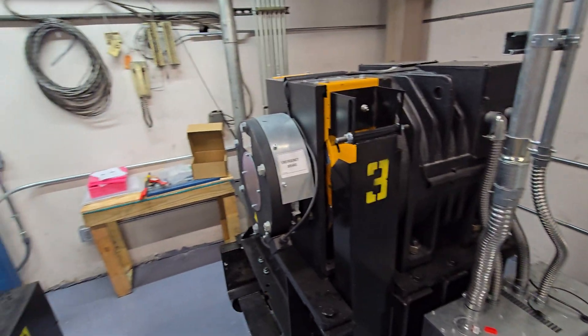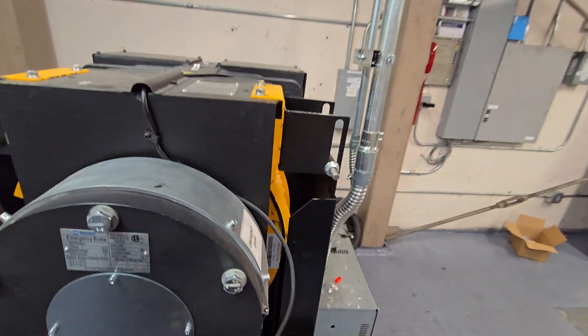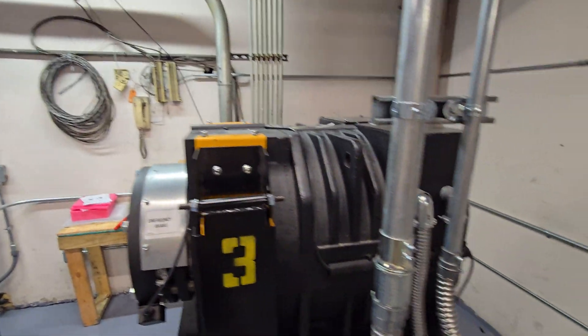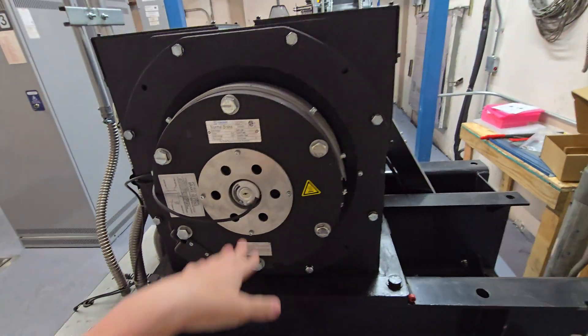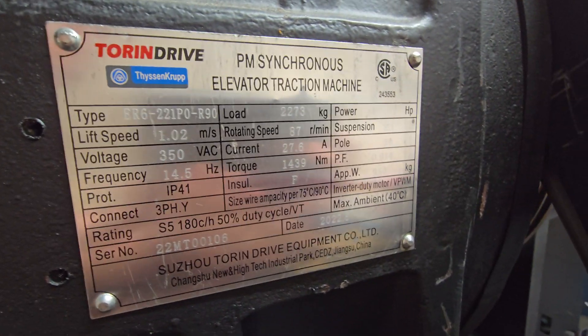Here are the regular car machines. These all use TorinDrive machines — kind of odd. This is a TKE installed. Here's your data plate. These machines are very compact. There's the brakes — the emergency brake and the normal brake. Synchronous elevator traction machine.